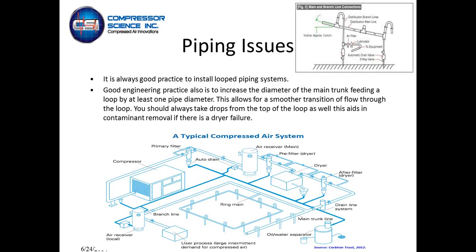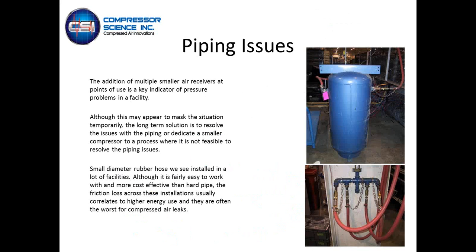As far as mainline and branch line connections, it's always recommended you take compressed air drops off the top of the header. These are just good engineering practices: if there is a dryer failure, you have moisture issues in the plant, and water then has to work its way up from the main distribution line to come down to your process equipment. We recommend installing drip legs on process lines that you can drain out if there is a dryer failure. At least you've got the capacity to deal with it.